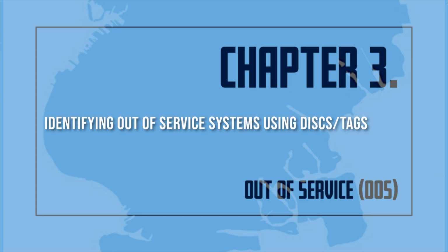Identifying out-of-service systems using disks/tags. Systems that are out of service, both planned and unplanned, shall be immediately identified by placing a tag at each of the following locations: fire department connections, system control valves, fire command center, or other clearly visible location in the lobby of the building indicating which system or part thereof is out of service.